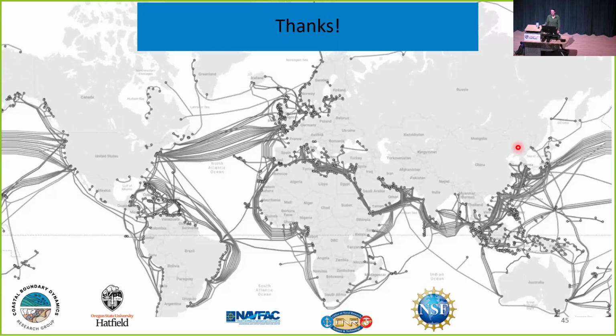Yes. So I'm going to pull that into two different pieces. The cable itself - you could imagine if we had a cable laid here on the floor, if it was a really soft cable, I could step on it here and squish it, and that part of the cable over there maybe would not respond very much. So that's the piece of like one section of the cable being strongly impacted by - if I pointed a heat gun at this section, it would warm up, and the section over there would not. So we can have strong variability in the cable itself.